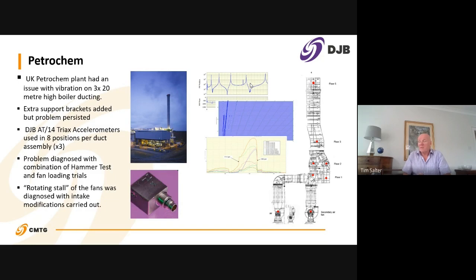And so they carried out, with the manufacturer, some intake modifications, which changed 2 things. They increased the size of the intake flow, but they also changed part of the S ducting type arrangement at the bottom, and they changed the ducting to make sure the air, when it came in, was not coming in at a slight angle, which was happening as well and was causing part of the rotating stall. So that's 3 typical applications.